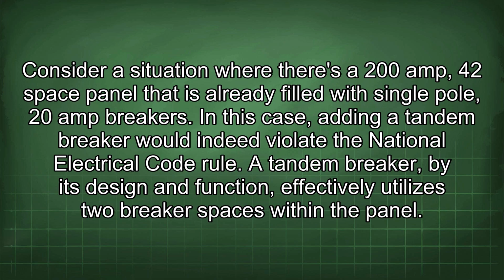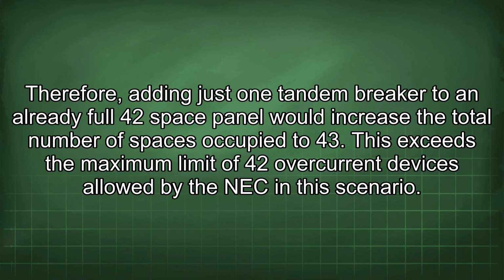Consider a situation where there is a 200 amp 42 space panel that is already filled with single pole 20 amp breakers. In this case, adding a tandem breaker would indeed violate the National Electrical Code rule. A tandem breaker, by its design and function, effectively utilizes two breaker spaces within the panel. Therefore, adding just one tandem breaker to an already full 42 space panel would increase the total number of spaces occupied to 43. This exceeds the maximum limit of 42 overcurrent devices allowed by the NEC in this scenario.